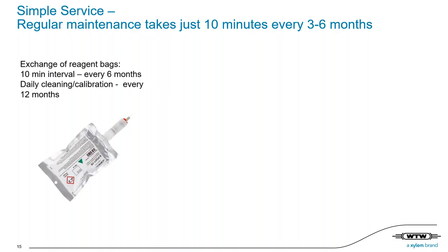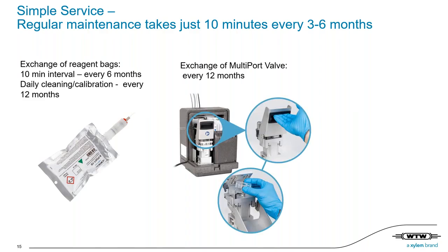As you've seen so far, we have designed the Alyza so it has minimal hands-on maintenance requirements with no expensive service contract required. So we really designed it with and for you. In total, maintenance takes just 10 minutes every 6 months at a 10 minutes interval. So let's see what has to be really done. Of course, part of the regular maintenance of all wet chemical analyzers is the renewal of the reagents. Thanks to the Chembags, it is as simple as never before. Just unscrew the old one and add a new one every 6 months. As I mentioned, the main spare part is the multiport valve, which has to be exchanged every 12 months. Just open the holder, take out the old one, and replace it by a new one, and that's it.